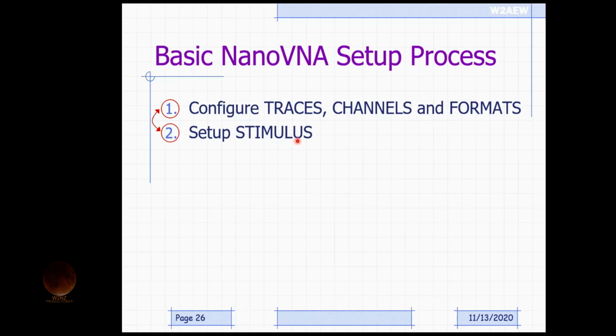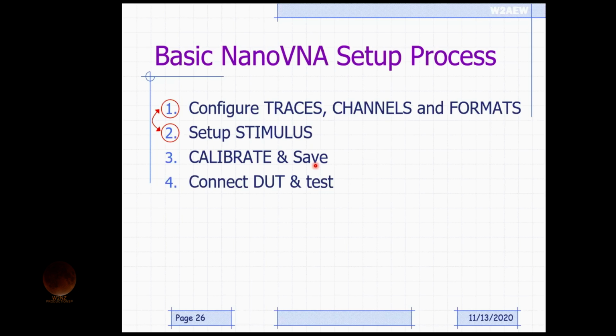Now, those two things can be interchanged. You can start off by setting the stimulus and then set and configure the traces and channels, but usually those are the two first steps that you do. The third step is to run that calibration. Now that I've established the stimulus, I want to run a calibration and then save it, so that now I've got it and I can go back and return and make the measurements. After that, I connect my device and I go and make my measurements, extract what I want to look at, do what I'm doing with it, and then I'm essentially done.